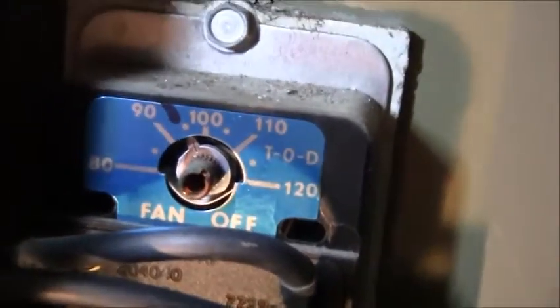Now normally without natural gas, because I have the valve shut off right now, you're not going to get your supply fan to come on because of this thermostat right here, and it's currently set at about 95 degrees Fahrenheit. I'm going to leave that alone. Normally these two black lines, one is connected on one side of the thermostat, one on the other side. What I did is I bypassed it by putting in a double tap spade terminal right there.